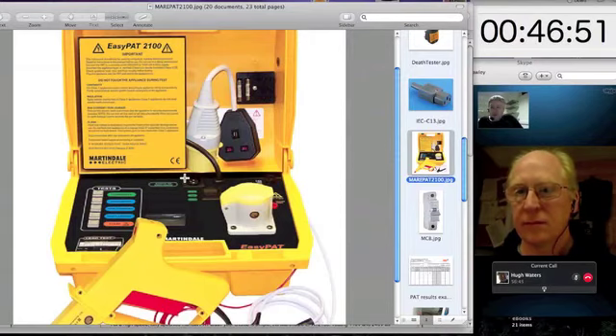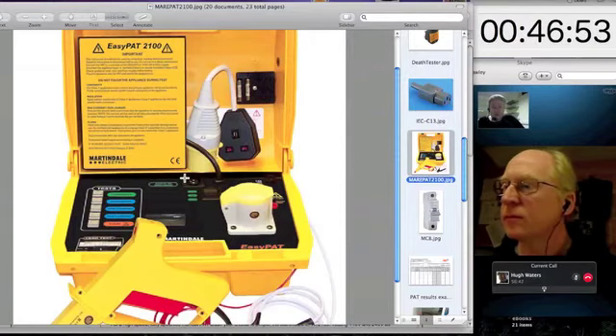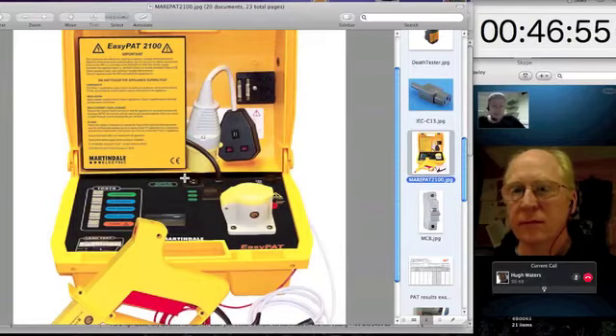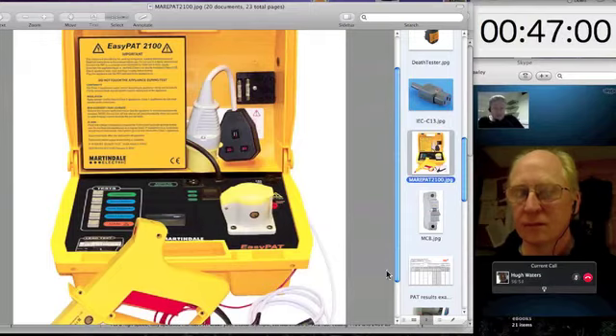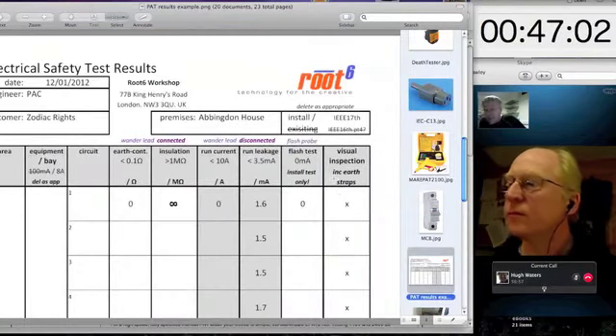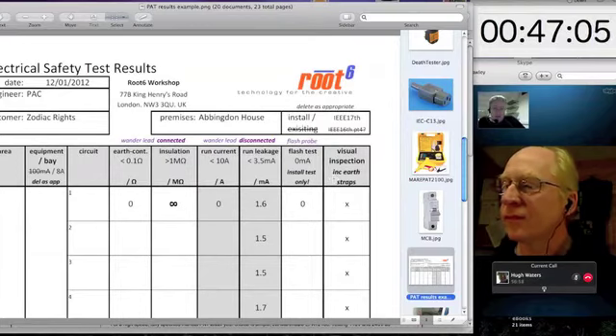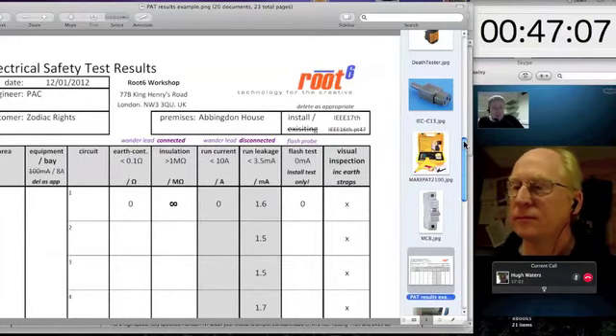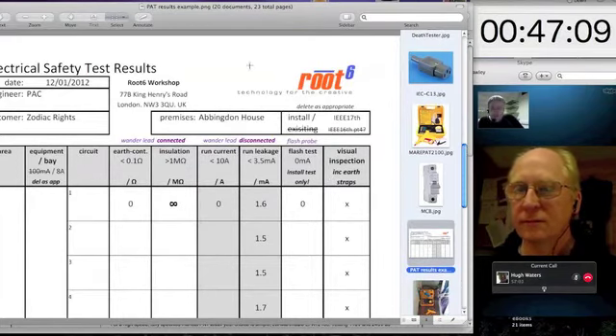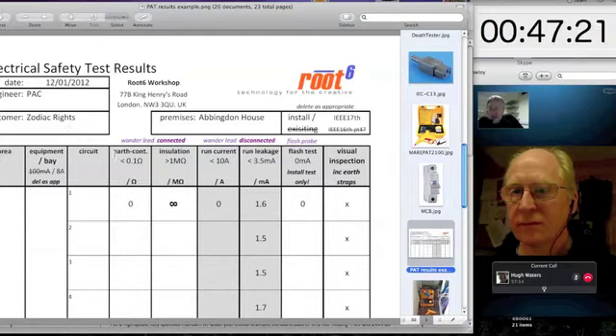And I've got a picture of a Martindale 2100, which is our preferred model of PAT tester. It's the one that we use. We have a couple of those. We use them on all our builds. And I've also popped up the test sheet that we issue. It's relevant not only for the equipment cabinet, but it can be used for an edit desk as well, and it has space to record all the circuits, and I try and construct these test sheets so that it drives the engineer through the correct way of doing it.